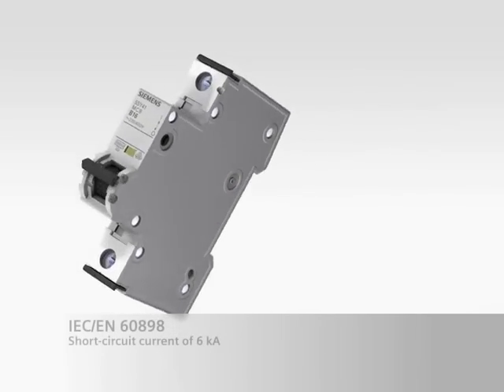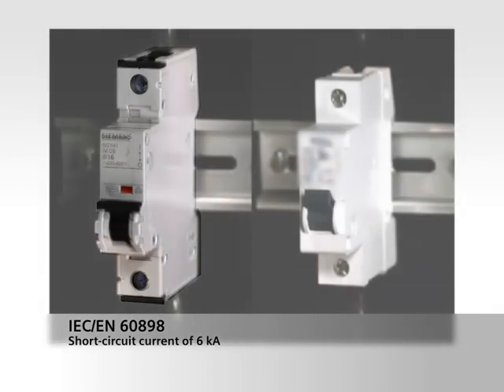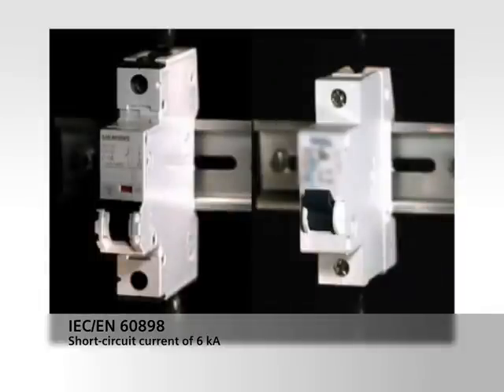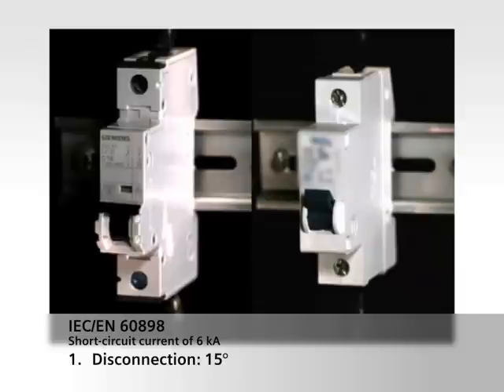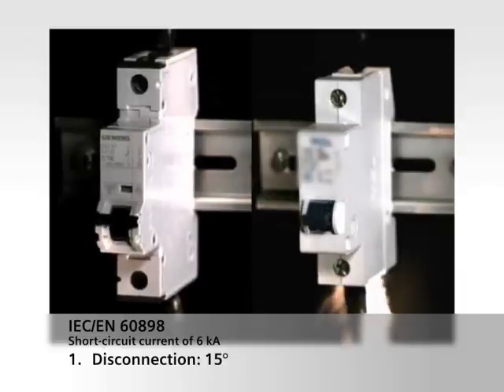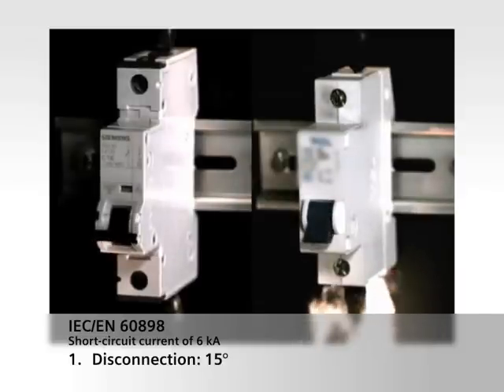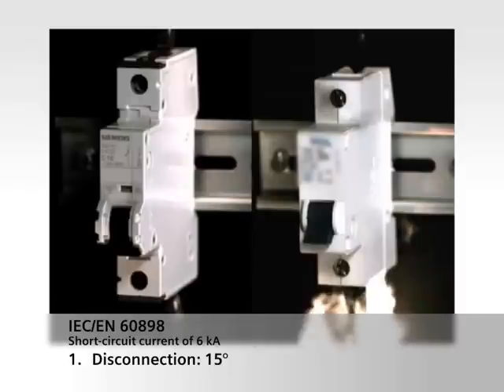A test is performed in compliance with IEC EN 60898. The miniature circuit breaker must be able to disconnect a short circuit current of 6 kA 3 times. We tested a Siemens miniature circuit breaker and, according to the manufacturer's data, a comparable device, currently available on the market. Even at this early stage, there are clear differences in switching behavior.